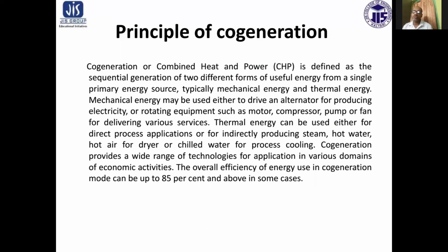Now, principles of cogeneration. Cogeneration, or combined heat and power, is defined as the sequential generation of two different forms of useful energy from a single primary energy source, typically mechanical energy and thermal energy. Mechanical energy may be used either to drive an alternator for producing electricity or rotating equipment such as a motor, compressor, pump, or fan for delivering various services. Thermal energy can be used either for direct process applications or for indirectly producing steam, hot water, hot air for dryers, or chilled water for process.